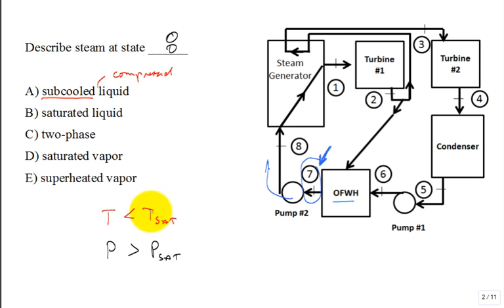If you want to confirm that it's subcooled, knowing the pressure, get the saturation temperature at that pressure and compare the actual temperature with the saturation temperature. If it's colder, we would say that's subcooled liquid.